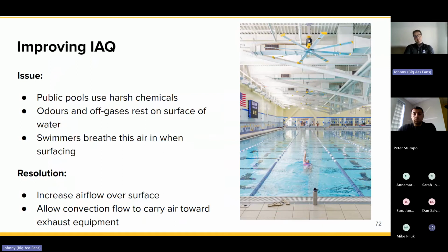Another environment you may not think of is a pool environment. Why do you need a fan in a pool environment? The biggest thing is actually to dissipate the chemicals. Oftentimes in these aquatic environments, you have harsh chemicals and poor air quality that hovers right above the surface of the pool. What you want to do with a fan is gradually push those off the surface, up the walls to the exhaust points. So you're never going to run the fans too fast - you do not want to speed up the process of evaporation or make people feel cooler than they need to, but get that gradual, imperceivable airflow, 40 feet per minute or less, just to wick away some of those chemicals in harsh breathing zone areas. So that's what we're doing in these types of environments.